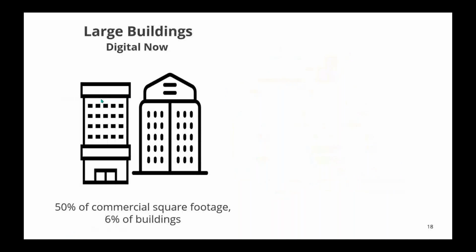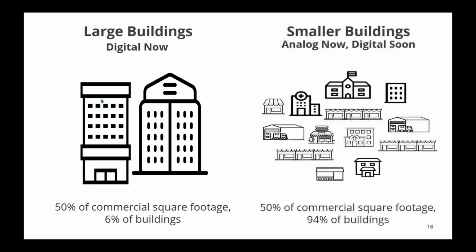Energy savings from systems integration can be attractive to building owners, especially for people with buildings larger than 50,000 square feet that already have a building automation system and may even be subject to building energy performance standards. Occupied standby mode is also feasible in some smaller buildings, usually with old-fashioned analog dry contact technology. But soon, thermostats with Wi-Fi or Bluetooth connections will support plug-and-play digital versions of occupied standby mode in smaller commercial buildings without full-blown building automation systems.